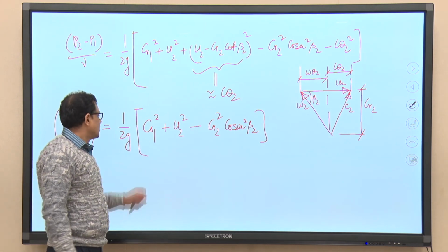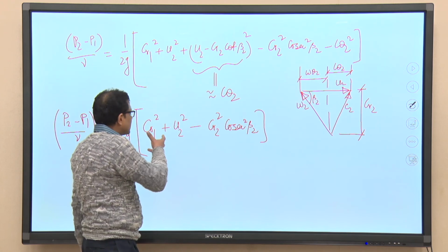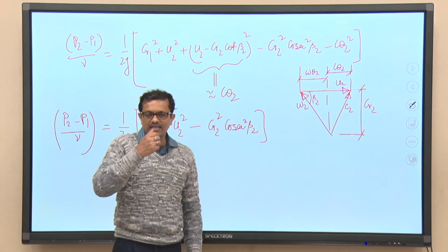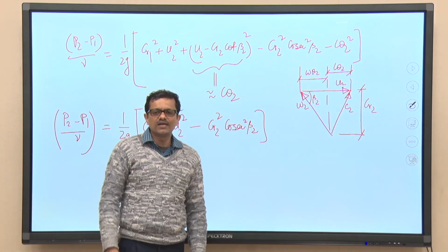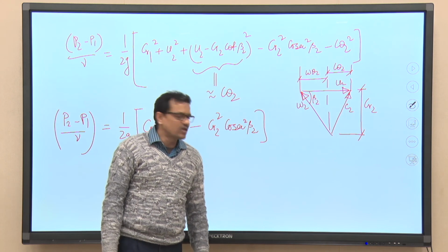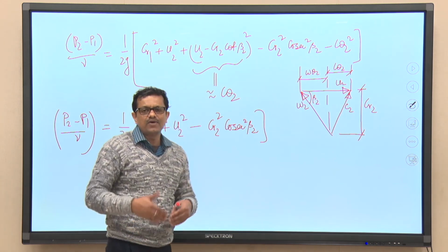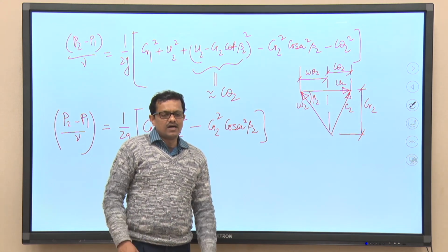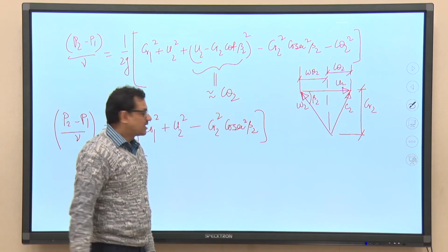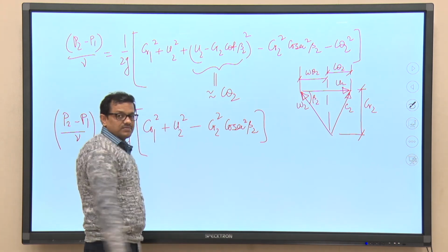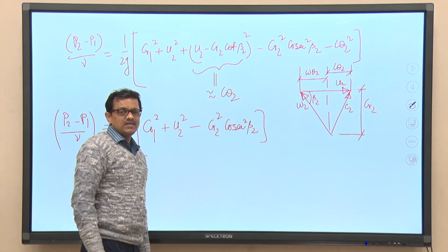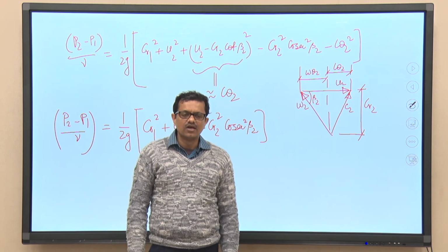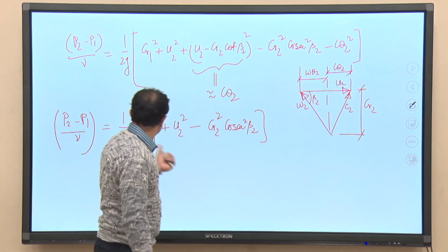So, what we can see is that the pressure rise can definitely be increased by increasing U2, that is what we have learned many times. That means we can increase R2 or we can increase omega, but increasing omega is not a viable solution. Again, if we keep on increasing R2, the impeller diameter at the outlet will increase, and that will be a problem from the mechanical balance point of view, also from the mechanical operational point of view. If we increase CR1, the maximum CR1 is C1. So, if we keep inlet swirl equal to 0, then the head developed by the pump can be increased.